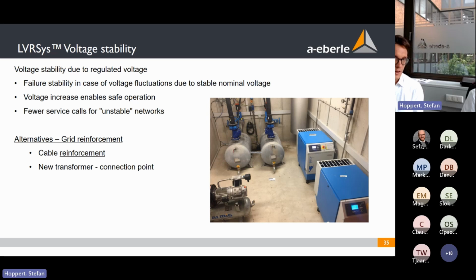The stability is given there, and if the voltage is increased, you have far fewer service calls. The only way to solve this issue on this side would be to reinforce the cables or the lines. So if you can imagine, for such long lines, to renew it, and then you're not even sure if it solves the problem for the whole time. Now in some years somebody will have the idea that everywhere has to be an e-mobility charging station, so then you have to renew it again, or you have to make different ways.